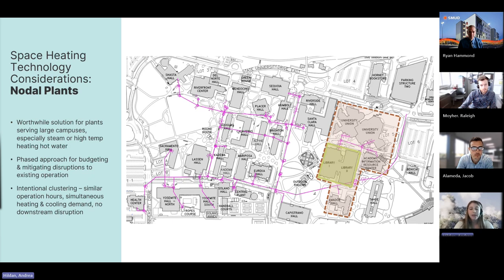And really there's 3 main benefits when I'm looking at this strategy. The first one is allocating a decent amount of space up front to serve multiple buildings rather than trying to do a spatial allocation for all 4 buildings, which can be quite challenging, as Jacob mentioned. A lot of former gas systems are usually indoors and tucked in smaller closets, so having to use technology like air-to-water heat pumps that are in new outdoor spaces can be pretty challenging to allocate on existing campuses.